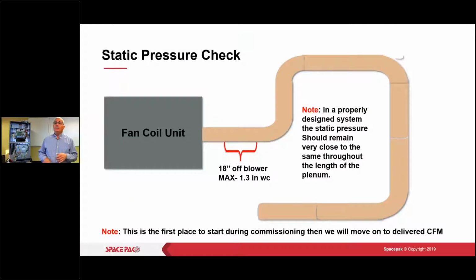Okay, so when we do set up the system, or let's say you change the old air handler, because we've got plenty of systems out there now where we've been changing air handlers because they're 20, 25 years old, 18 inches off that blower, we want to take our pressure test, our static pressure test, and that's where you check that. Now, older systems we balance by adding all these extra drops. Newer systems today we can balance right at the air handler. You have to follow the instructions in order to do that.